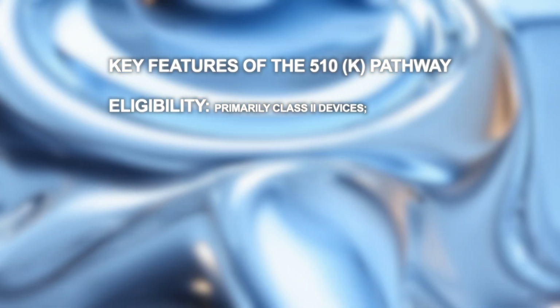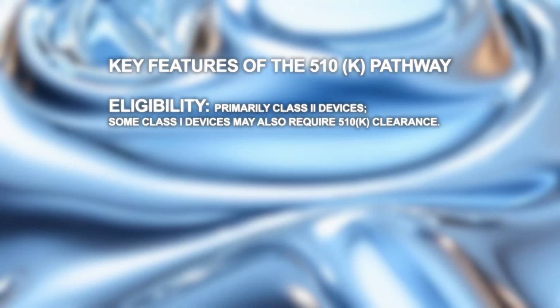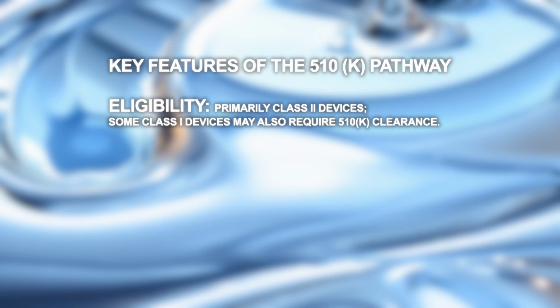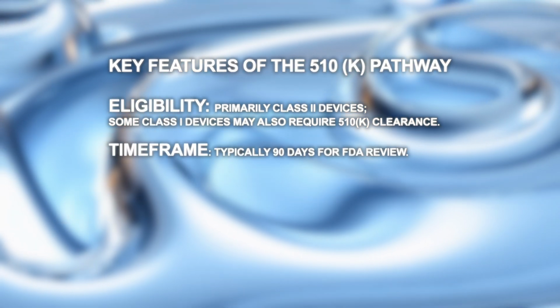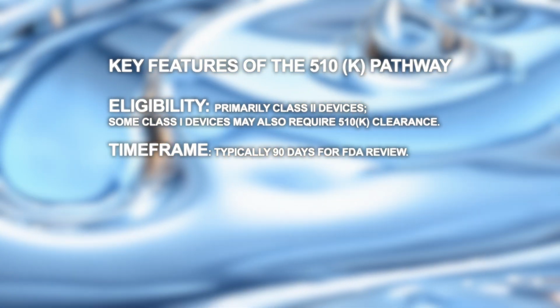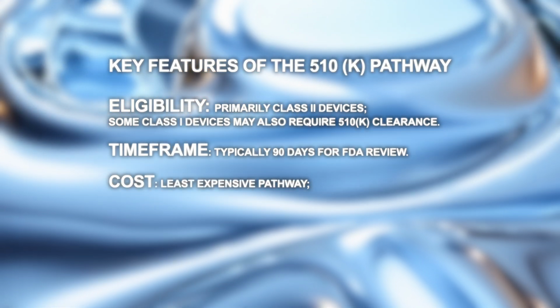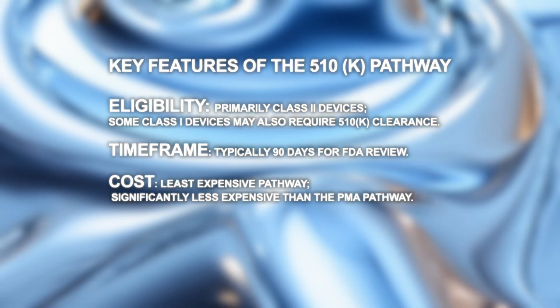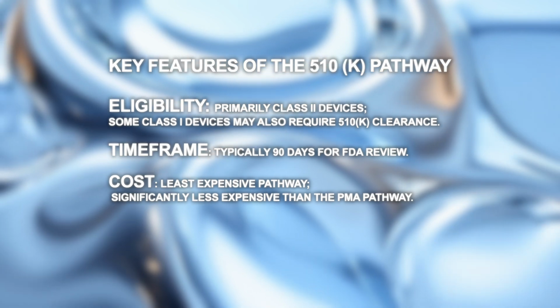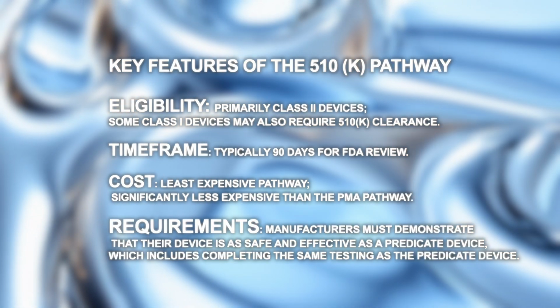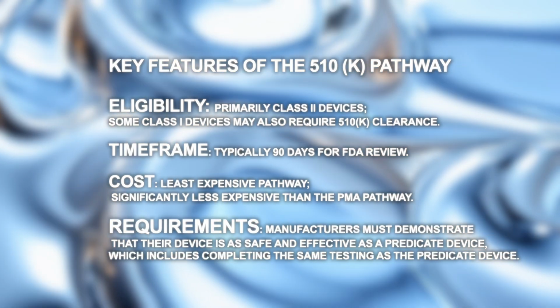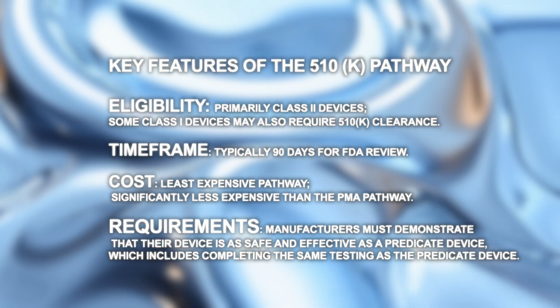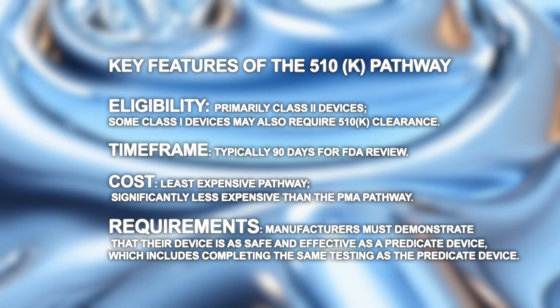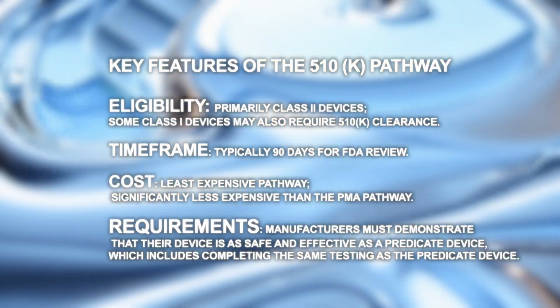Eligibility includes primarily Class 2 devices, although some Class 1 devices may also require 510K clearance. The time frame is typically 90 days for FDA review. In terms of cost, this is the least expensive pathway, significantly less than the PMA pathway. Finally, the main requirements are that manufacturers must demonstrate that their device is as safe and effective as a predicate device, which includes completing the same testing as the predicate device.